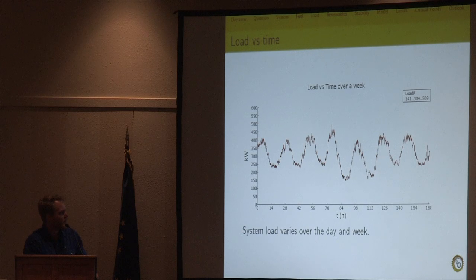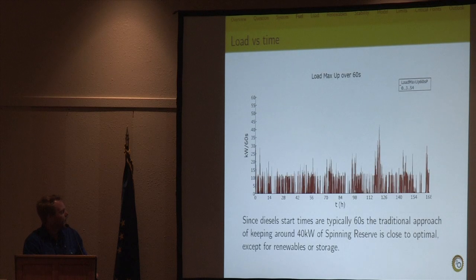It's called spinning reserve. In this case, when you look at second-by-second changes, the maximum change is around 40 kilowatts per second. Now you want to know how much your load can grow in about a minute. In an emergency, you can bring on a small diesel within a minute if you're keeping it in hot standby.